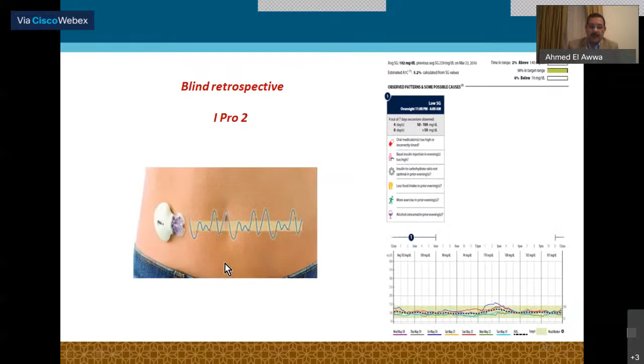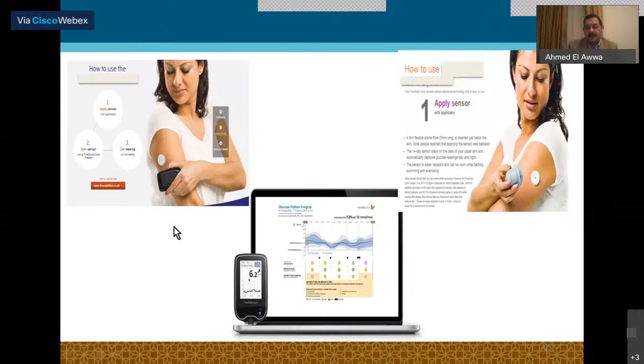The intermittent scan means what? It's not real-time data. You need to make a 1 second scan. You just swipe this device against this small sensor, and you will have the data instantly on the screen. And nowadays it's used with the mobile even. After making this 1 second scan, you will have the retrospective data for 8 hours. And you can take this data, it's validated by the FDA to take action on it immediately. And now, with the new versions, it includes some alarms as well.